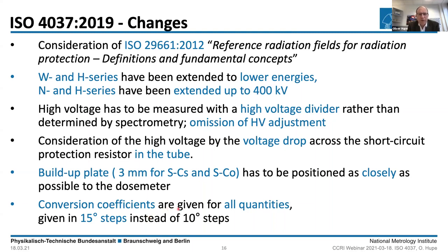And the conversion coefficients are now given for all quantities. That means for 3 millimeter depths as well. And it's given in 15 degree steps instead of 10 degrees, because for the type test requirements, you always need 15 degree steps.